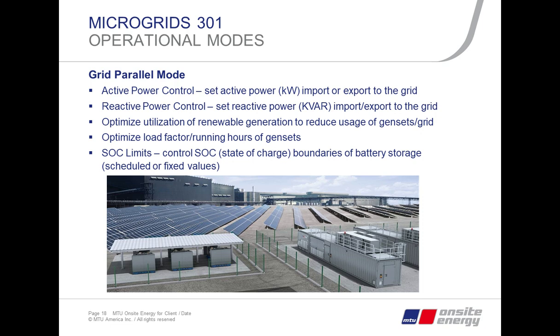We'll still have optimization if we have renewables, to reduce the use of gensets and the grid by producing as much power as we can through renewables, avoiding running gensets or importing from the utility. We try to optimize the load factor and running hours of the gensets, so when they run, they run at an optimal load factor. And if there's battery storage, we also want to control its state of charge, keeping it in an optimum range for battery longevity, and so it's available to be charged from renewables or to discharge power when needed.